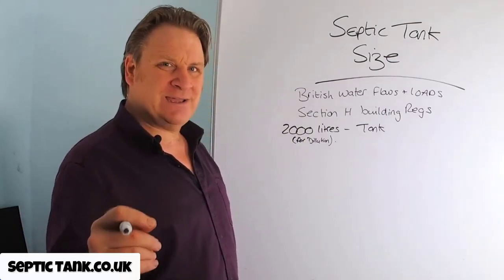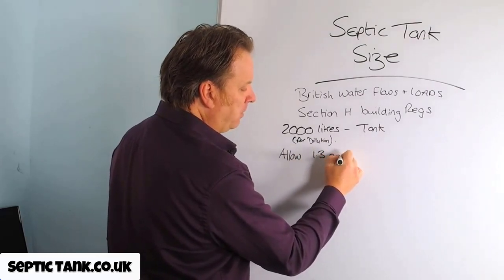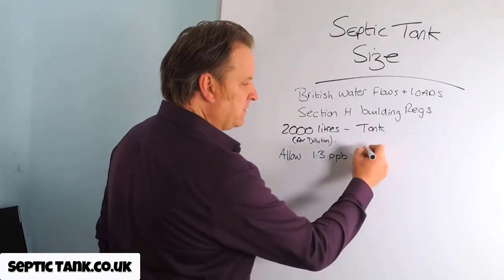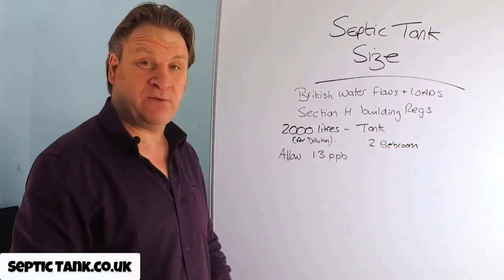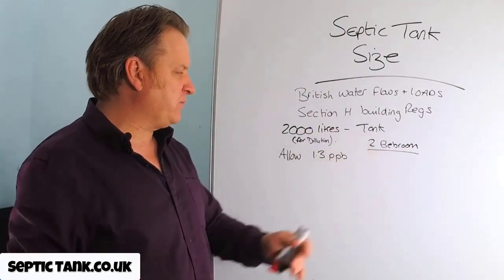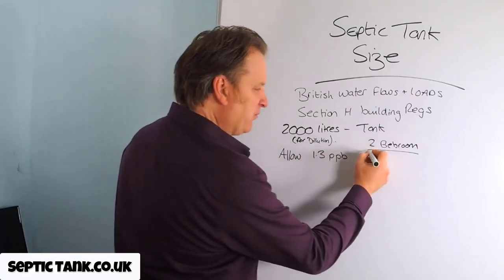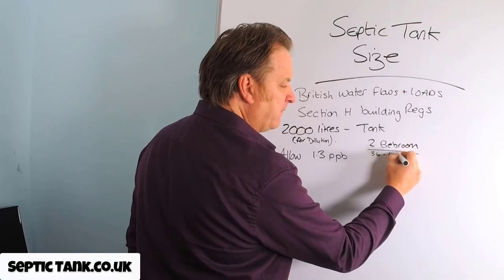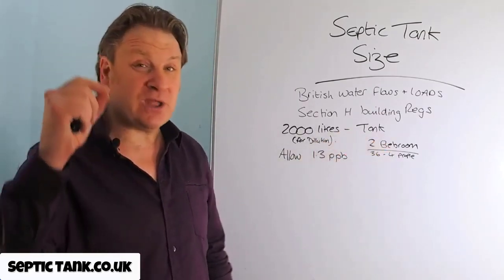The government calculator tells you that you have to allow 1.3 people per bedroom. So let's make this easy — let's say you've got a two bedroom house. This could be a new house or you could be replacing your old system. So there are two bedrooms: 1.3 plus 1.3 is 2.6. I don't know where they get the 0.3 or the 0.6 from. So two bedrooms gives you 3.6, and you'd round that up to the nearest person — so that would be four people living in that house according to the government.